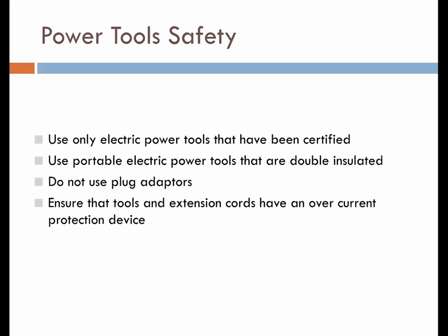Use portable electric power tools that are double-insulated or properly grounded with a manufacturer-installed 3-prong plug. Do not use plug adapters; match the plugs of electric tools with the power source outlet. Ensure that tools and extension cords have an overcurrent protection device — for example, a panel-mounted circuit breaker or inline fuse.